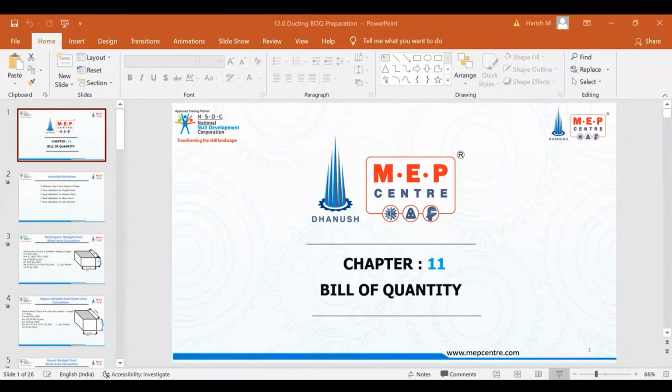So then if you come to the round, for round duct, the formula is pi into d into l, pi dl. Okay. So diameter is 1000 and length is 2500.